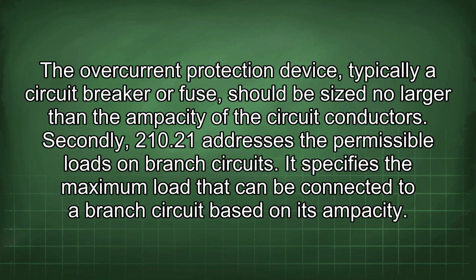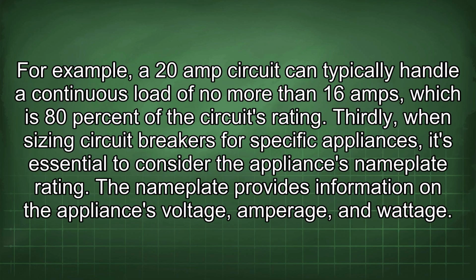The overcurrent protection device, typically a circuit breaker or fuse, should be sized no larger than the ampacity of the circuit conductors. Secondly, 210.21 addresses the permissible loads on branch circuits. It specifies the maximum load that can be connected to a branch circuit based on its ampacity. For example, a 20-amp circuit can typically handle a continuous load of no more than 16 amps, which is 80% of the circuit's rating.